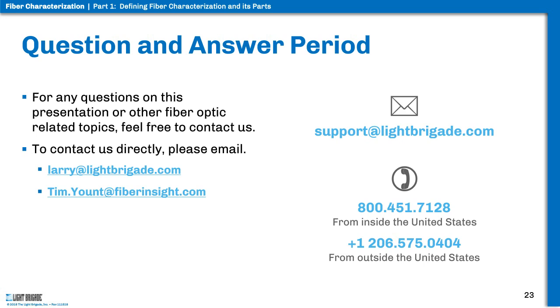Another question: Should the insertion loss test be done bidirectionally? Yes — recommended, yes. It's not absolutely required; some people choose to do it in one direction. If you had installed brand-new fiber all exactly the same type, you might be okay testing in one direction. But the standards recommend bidirectional testing, and that is the way to get the most accurate results — test bidirectionally, average the results, and use that information as your values against your link loss budget.